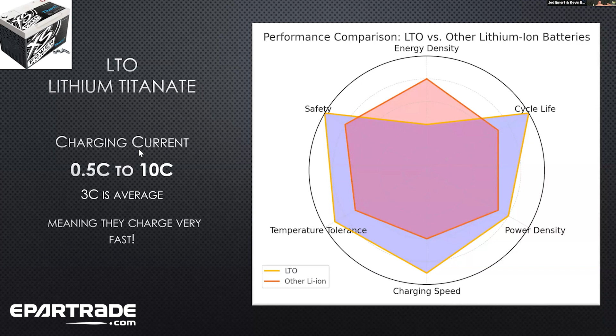And charging, now this is an amazing data point. You can charge LTO up to 10 C, that means 10 times its amp hour capacity. That would be charging a battery full in 6 minutes. Wow, you can see you can slam the energy into LTO batteries. That's why this is the battery of choice for, let's say, hybrid racing, where you're slamming energy into a battery, taking it out of a battery, something that can handle that kind of in and out fast. A lot of batteries can discharge quick, but the LTO can take it quick.